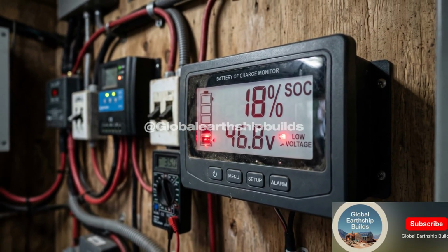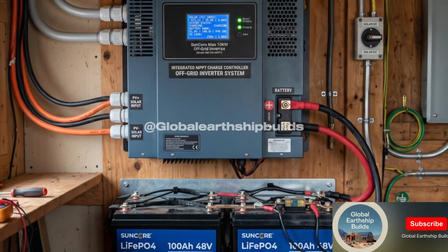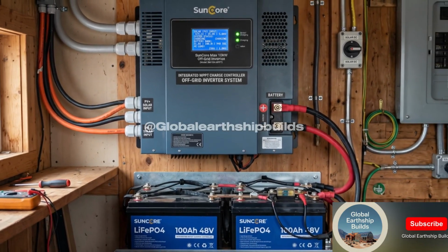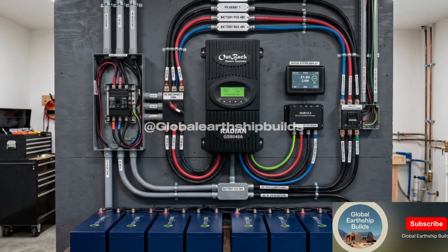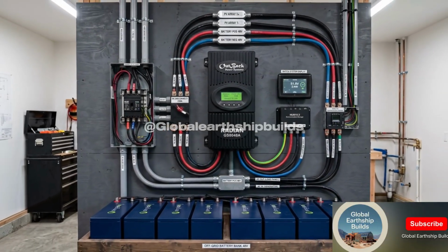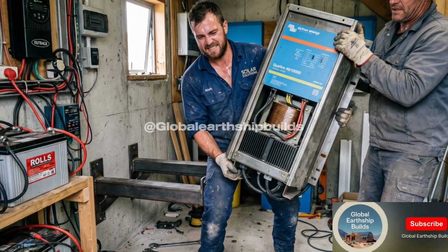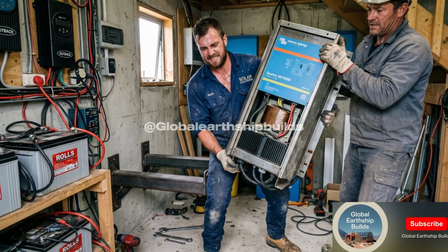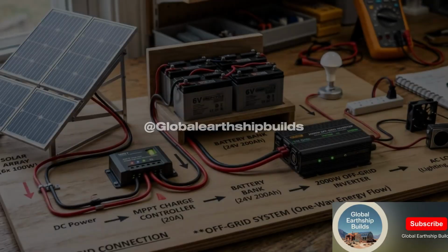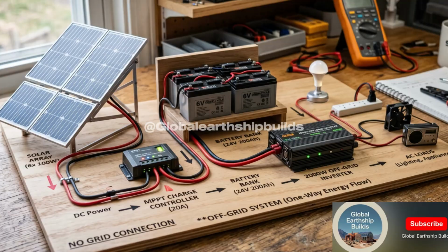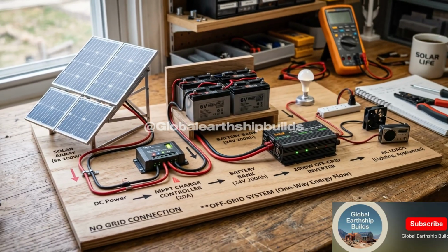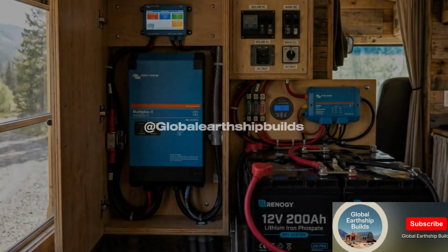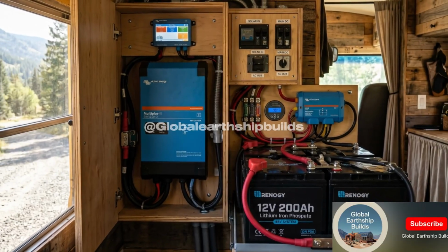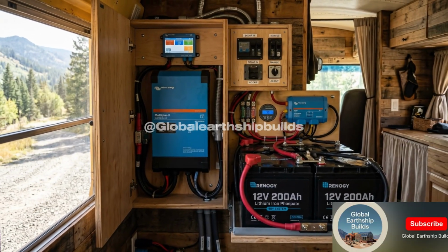Because of this, off-grid inverters are typically built with extremely high surge capacity. You need that surge power to start motors, compressors, well pumps, and air conditioners. Transformerless inverter designs are often weaker here. True off-grid inverters built on transformer-based architecture, like the Victron Multi-Plus series or the Outback Radian, can push 2 to 3 times their continuous rated power for short burst starts. That robustness is one of the things you are paying for.